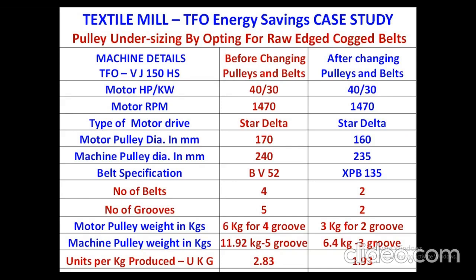They achieved energy savings. I don't talk about energy savings alone, I say the units per kg, UKG, the specific energy consumption, was reduced by 32%, because they were able to ramp up their speed, because there was dead wood in between on the pulleys and belts. There it is corrected automatically, and the energy saving is done. More than the energy savings, the productivity improvement is also seen by reducing the transmission and distribution loss from the motor to machine.